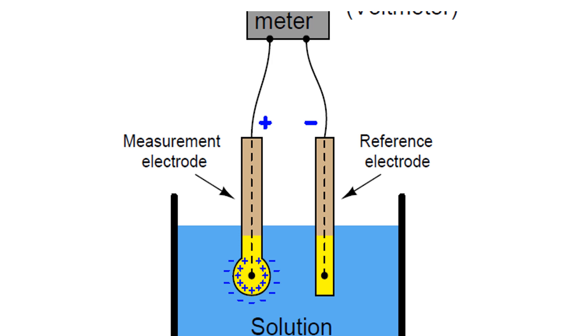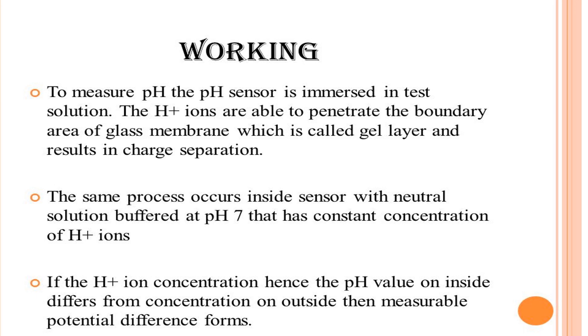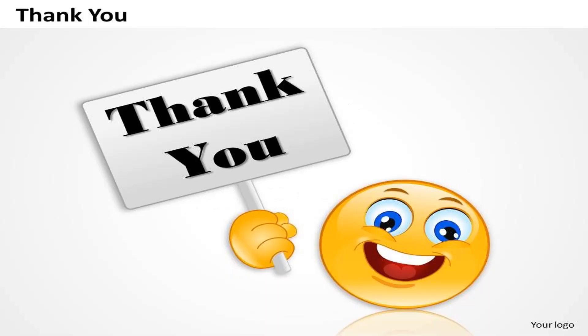To measure the pH, the pH sensor is immersed in the test solution. Hydrogen ions penetrate the boundary areas of the glass membrane, called the gel layer, resulting in charge separation. The same process occurs inside the sensor with a buffer solution at pH 7 that has a constant concentration of hydrogen ions. If the hydrogen ion concentration on the inside differs from the concentration on the outside, a measurable potential difference is formed.